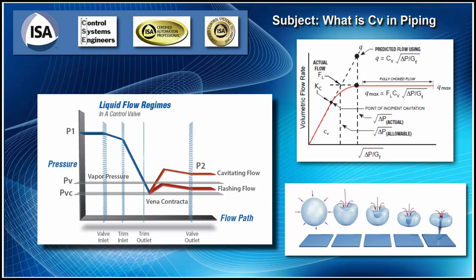It's called a microjet. The bubbles actually implode on themselves from the back and shoot out the front as a microjet, hit your metal, and actually melt the metal away. These bubbles become hot as the sun. They have pressures up to 100,000 PSI, maybe 3,000 K of temperature. You can get way up there. It gets as hot as the sun.